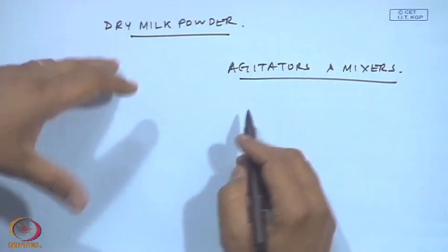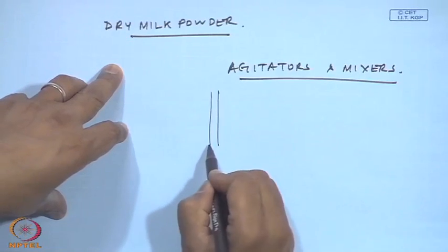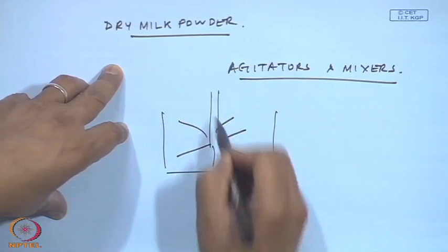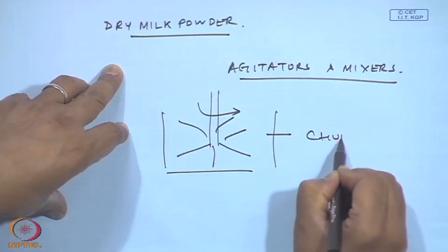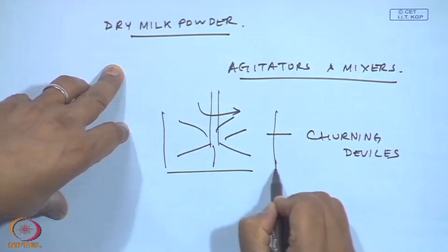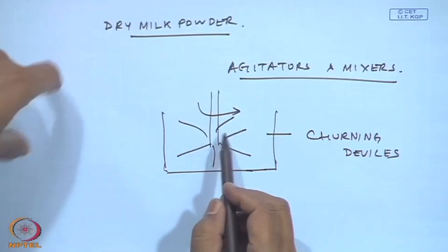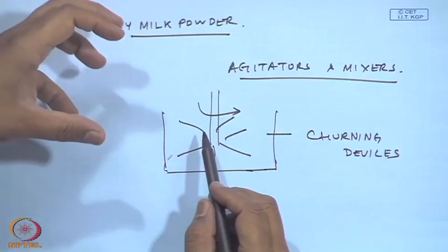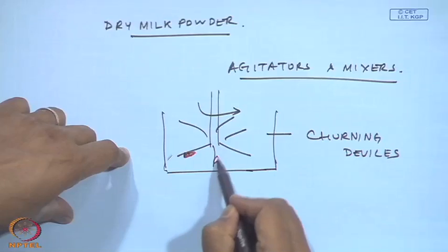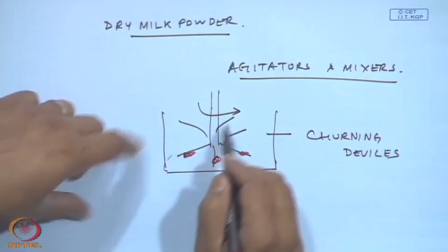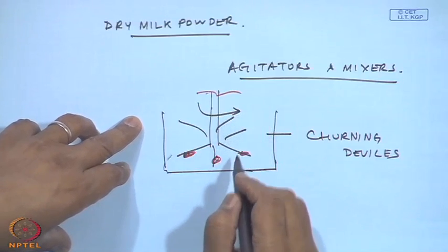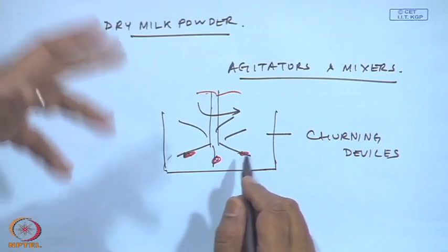Okay. Agitators and mixers are nothing but high speed churning devices in a tank. Again the same thing: if I feed in certain material which is susceptible to moisture and becomes sticky, it will stick to the blades. And then, because this is rotating, it goes into unbalance, and finally some fine day this thing has failed, because of excessive fatigue loading. Again these things happen.